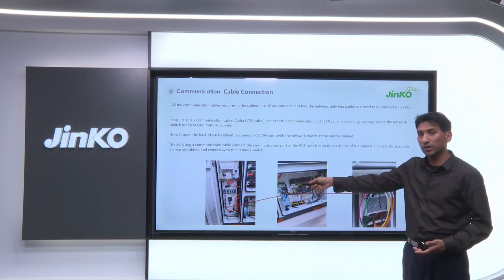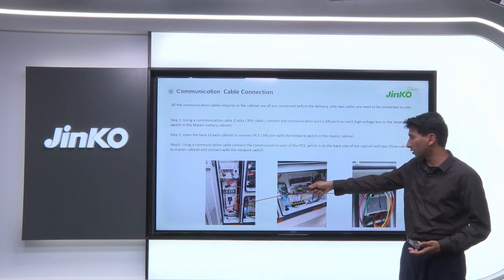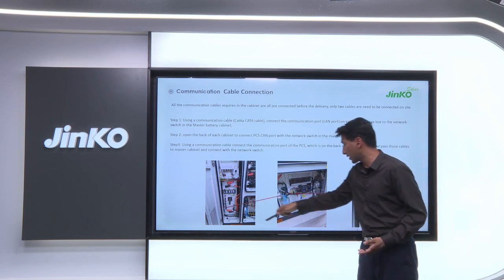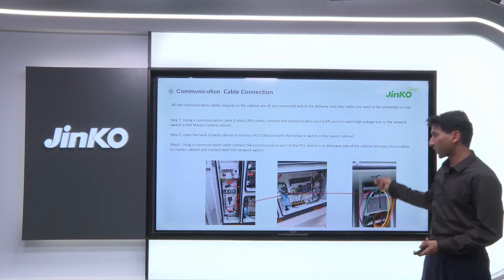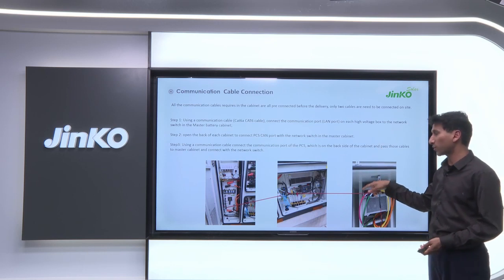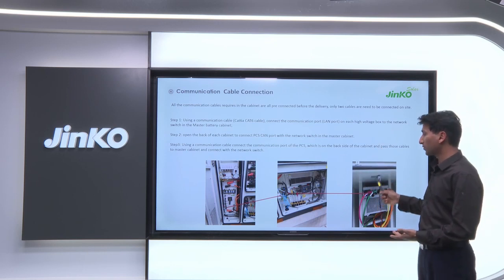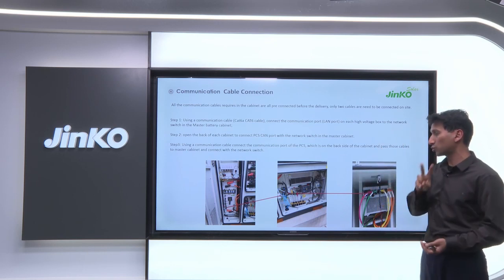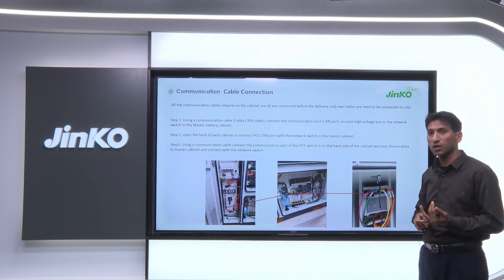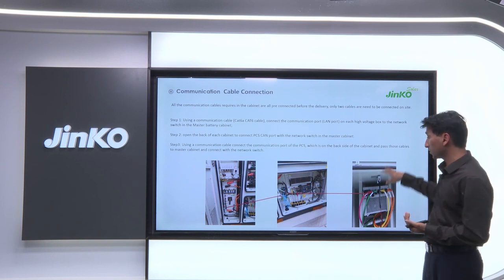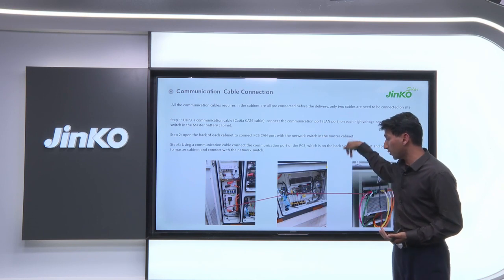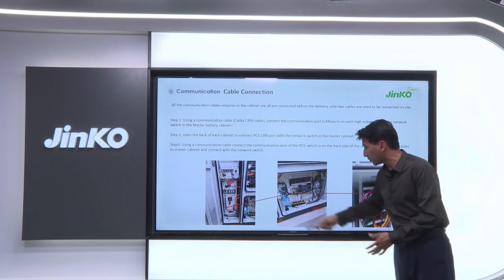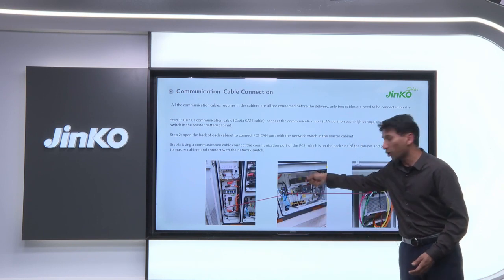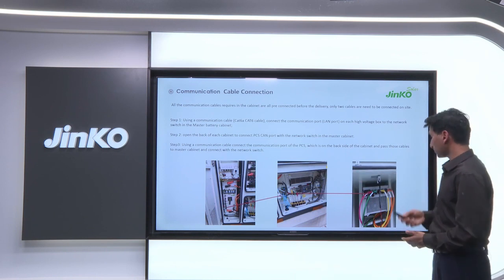There is no cable here. You will connect the same kind of cable from this place, and connect it to the network switch. This practice has to be repeated for each cabinet, not just one. If there are 5 cabinets, then for each cabinet you have to use 2 communication cables, one for the HV box, one for the PCS, and then you take all the cables down from there, route them up inside here, and connect all of them to the network switch.